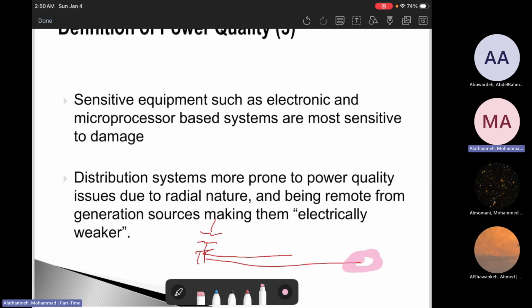So the last customer of the network will see the more frequent problems. All of this, they will be impacted. Again, the end user will struggle, because we can call this a weak grid, a grid that can be impacted easily by any small disturbance or any small power quality problem. In Jordan, many low voltage and medium voltage feeders are radial, as I draw here, this is a radial, not a ring. So on the radial, the end customer will see some problems.